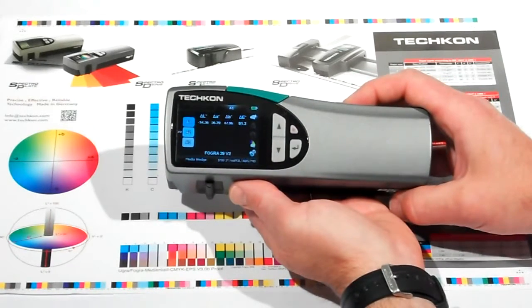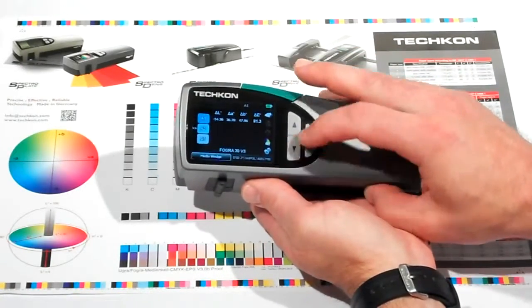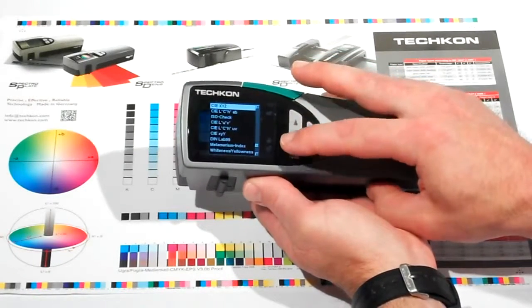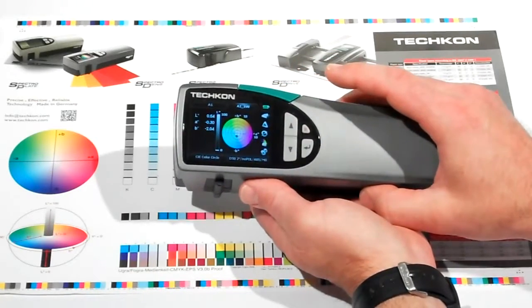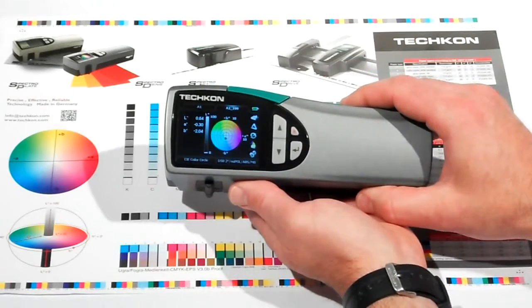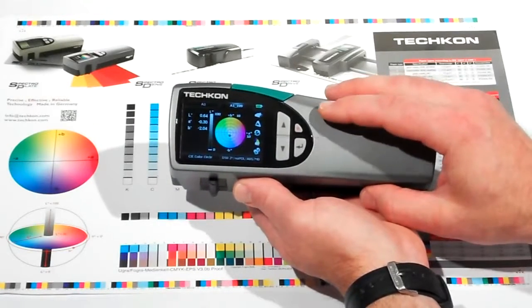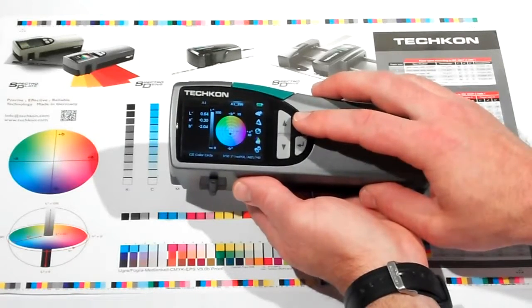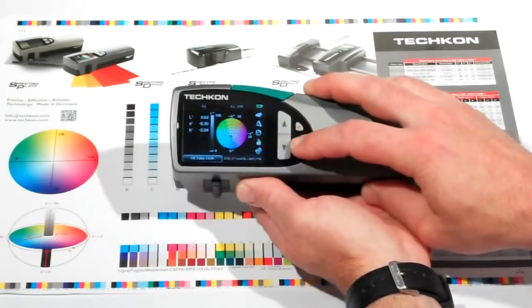The new SpectroDens is equipped with a high-resolution color display, designed to be more intuitive and to improve productivity by enabling a visual representation of CLAB values. Navigation consists of a down arrow and an up arrow, so you can navigate to the feature or function you wish to select. Once you've highlighted what you want to select, you hit the enter button and that feature is selected.